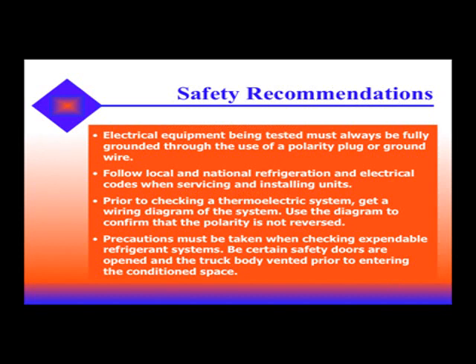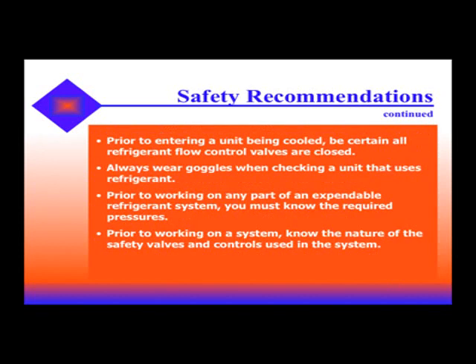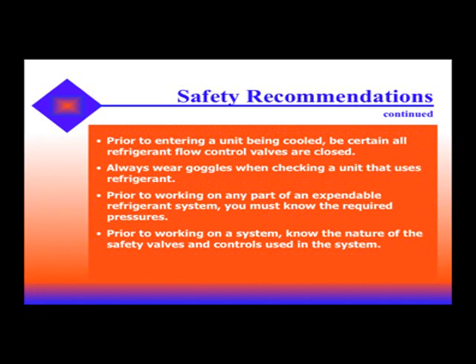When dealing with any specialized refrigeration, electrical equipment must be fully grounded by use of a polarity plug or ground wire. Follow local and national refrigeration and electrical codes when servicing and installing these units. Prior to checking a thermoelectric system, get a wiring diagram of the system and confirm that the polarity is not reversed. Be careful when checking expendable refrigerant systems — be sure that safety doors are open and the truck body is vented prior to entering the conditioned space. Prior to entering a unit being cooled, be sure that refrigerant valves are closed. Always wear safety goggles when checking a unit that uses refrigerant. Prior to working on any part of an expendable system, you must know the required pressures, and know the nature of the safety valves and controls used in the system.